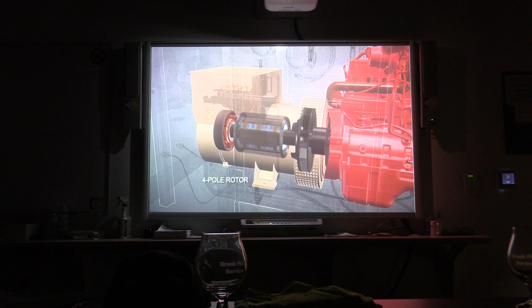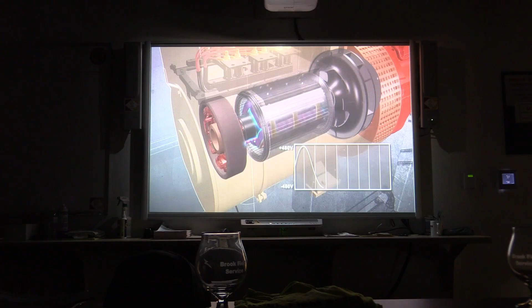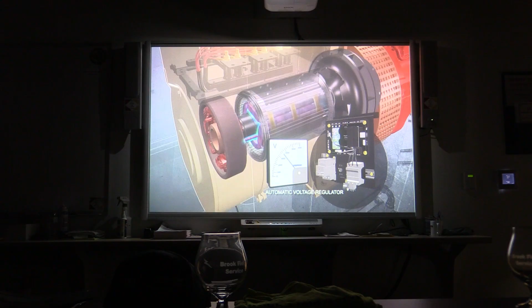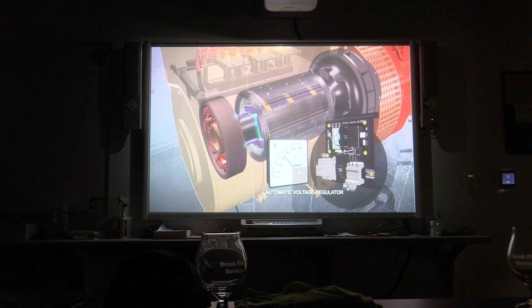Because the magnetic field builds and subsides, voltage fluctuates between positive and negative peaks, known as alternating current. The stronger the field, the higher the peaks. Ideally, voltage levels should be consistent so constant power is provided under load. To do so, an automatic voltage regulator, or AVR, adjusts the magnetic fields as needed. During heavy power demands, voltage decreases, causing the AVR to increase the magnetic field. Conversely, when power demands are low, the AVR tempers the field.